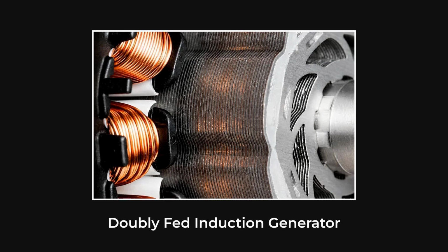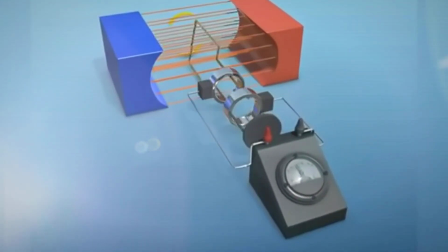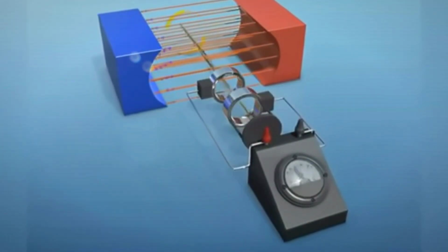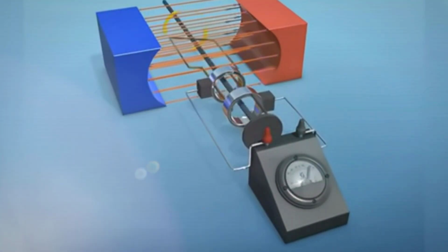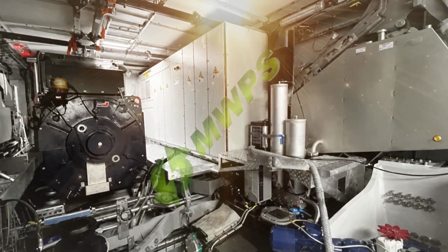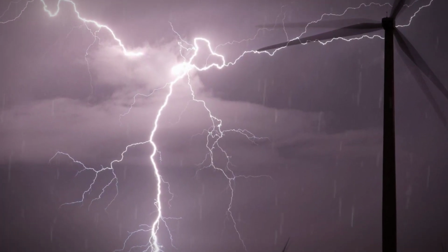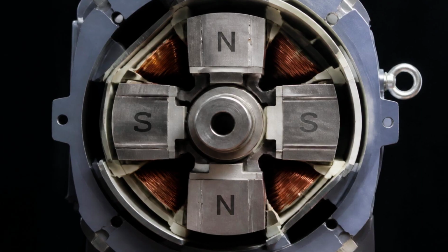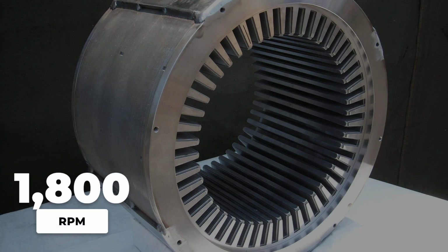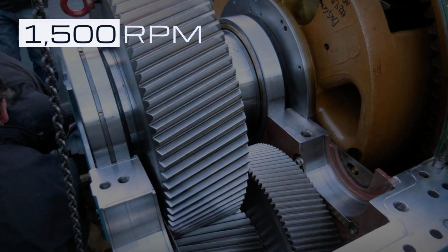Inside the nacelle, the generator is a doubly fed induction machine. A rotor wound with copper coils spins inside a stator lined with matching coils. And as the rotor turns, the interaction between their magnetic fields converts mechanical rotation into alternating current. The principle is simple. The reality is brutal. With 4 magnetic poles, the math demands exactly 1,800 revolutions per minute to produce 60 Hz. The gearbox delivers roughly 1,500 revolutions per minute. The wind decides the rest.